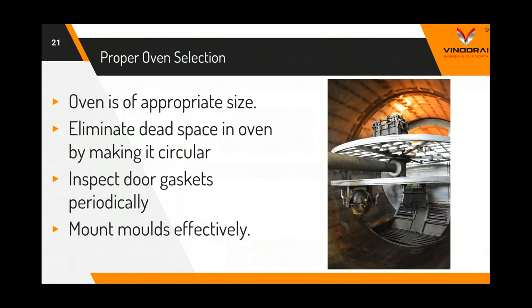If you place it offset, you need to heat more of the air and the rest of your furnace before the mold would actually receive the heat. So if the mold is placed at a location which is receiving the hit of the air coming from the blower directly, it would result in a smaller cycle time and hence lesser fuel consumption.